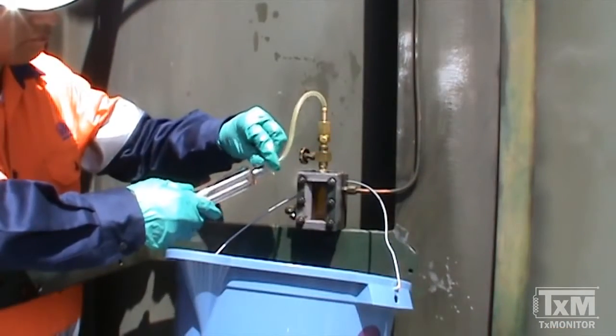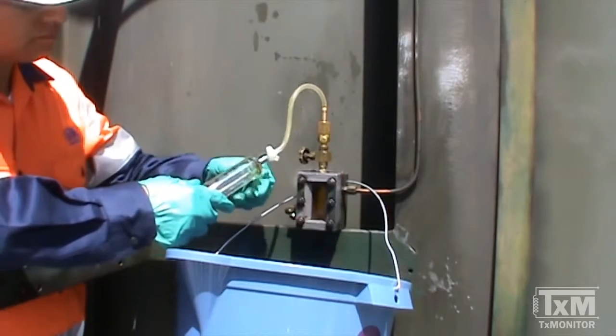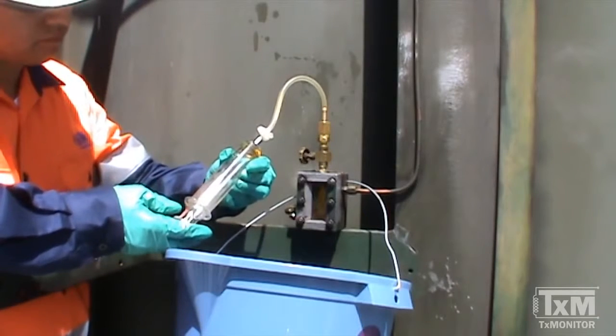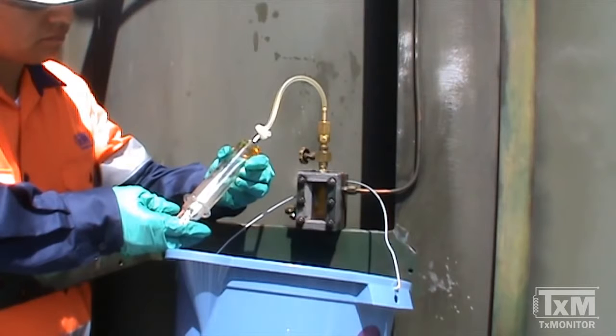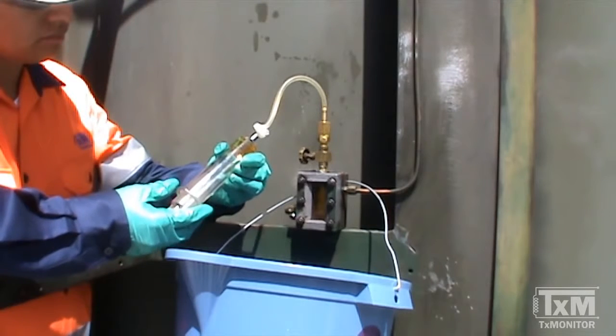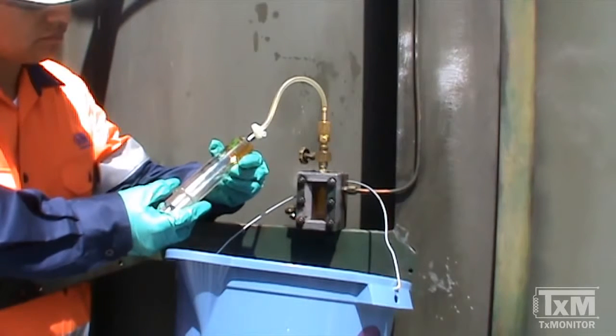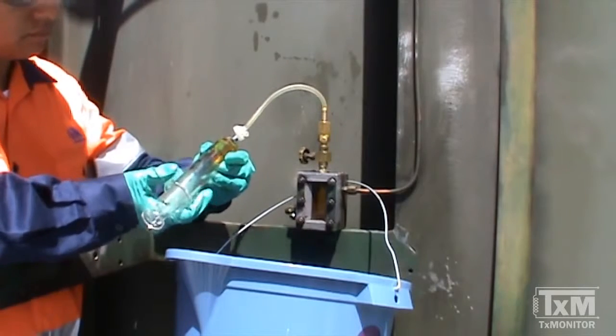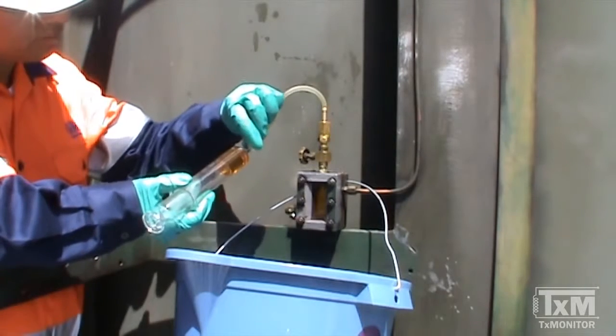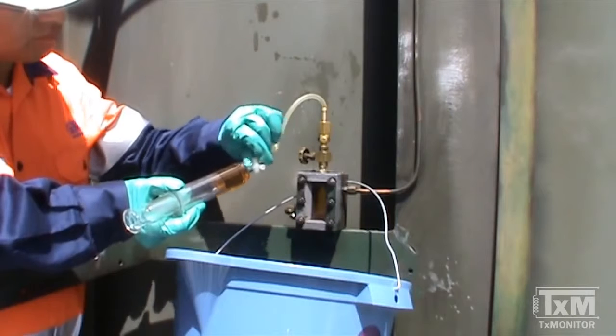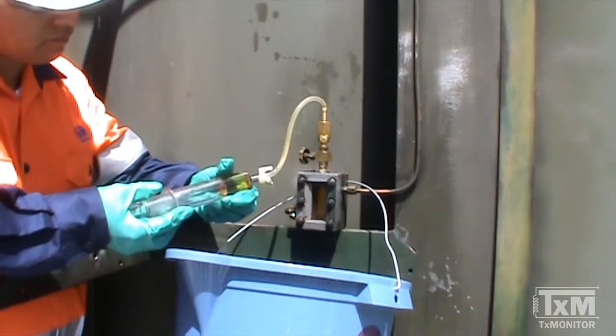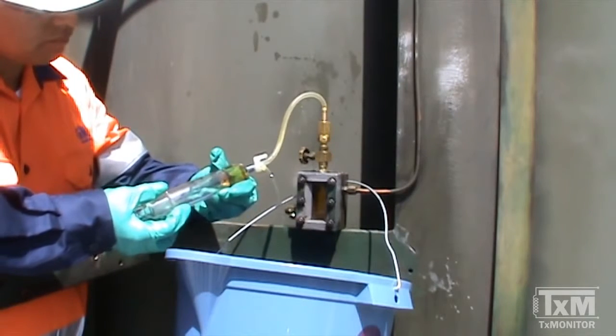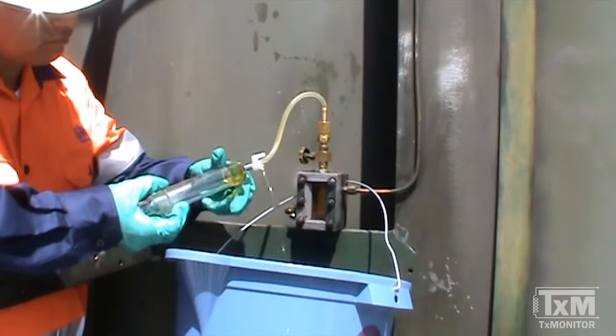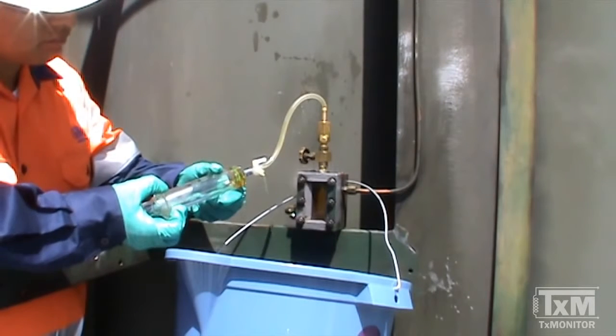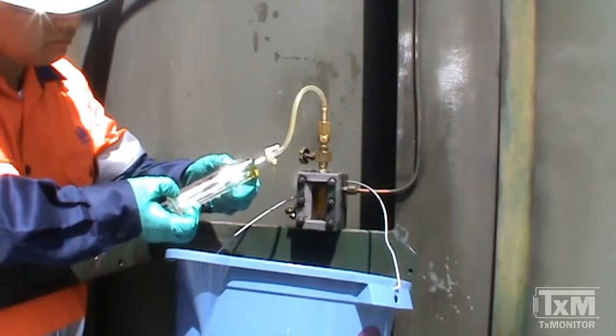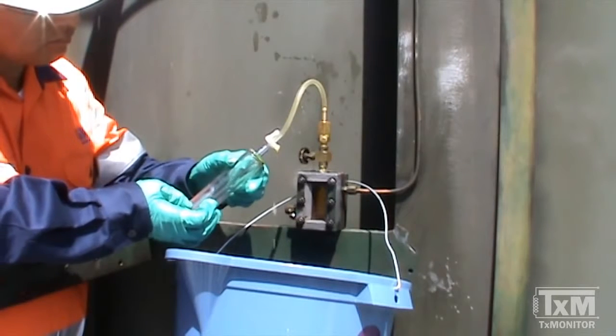Attach a suitable adapter and flush approximately half a litre of oil to clean the sampling port and discard the oil that might have been stagnant in the lines. Depending on the size of the transformer and the length of the lines connecting the sampling device for the Buchholz relay, it may be necessary to flush additional oil to ensure a representative sample is being obtained.